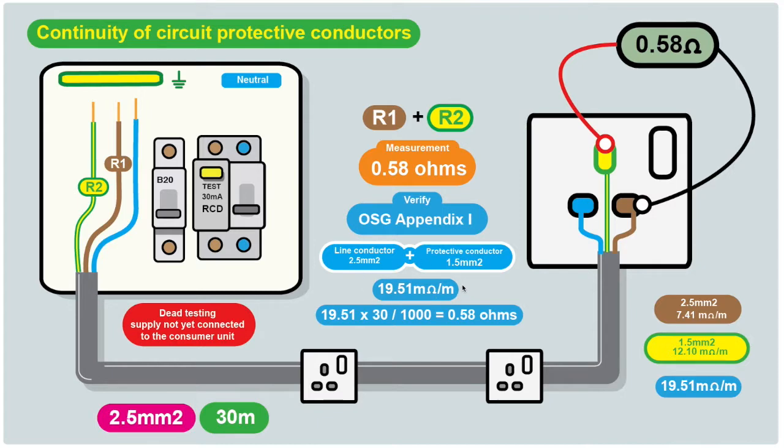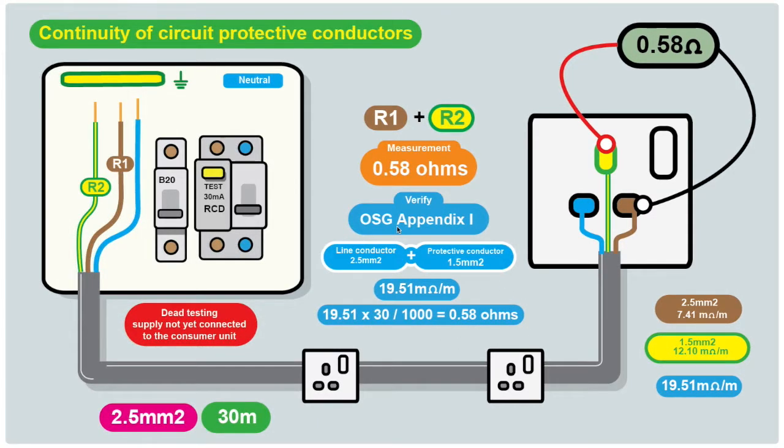It's some simple maths. All we need to do is times 19.51 milliohms by 30. Don't forget that's the length of the circuit. You get an answer and we divide that by a thousand to convert the milliohms into ohms. We've done the maths and the maths confirms a reading of 0.58 ohms for the length of the circuit, and that correlates with the measured reading that we took with our meter.